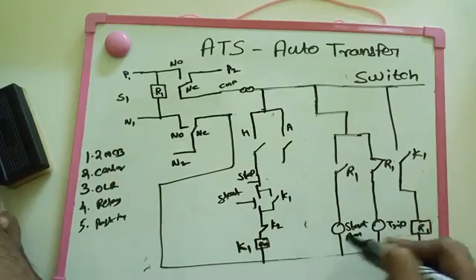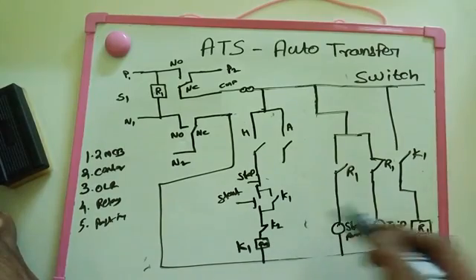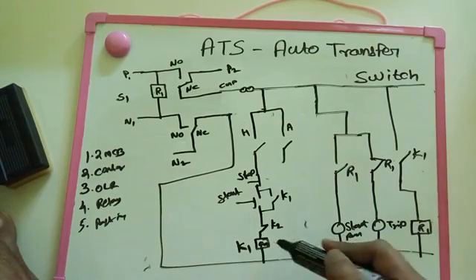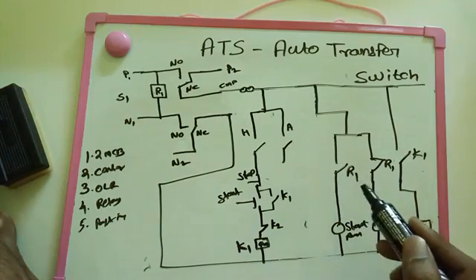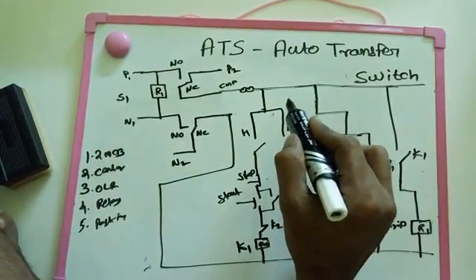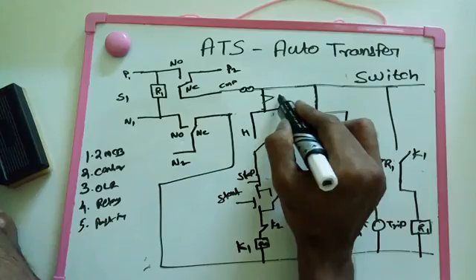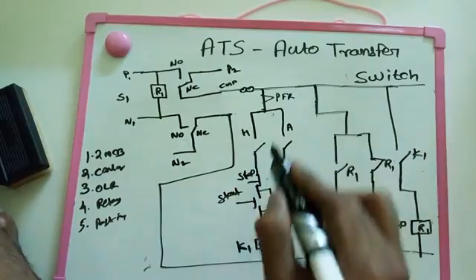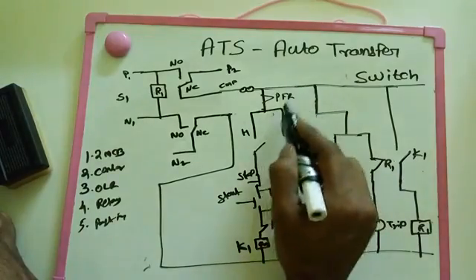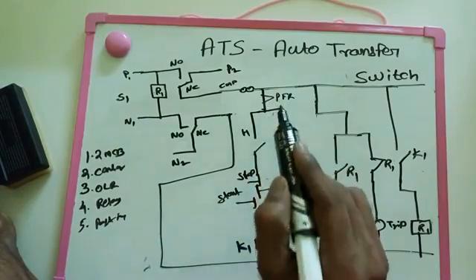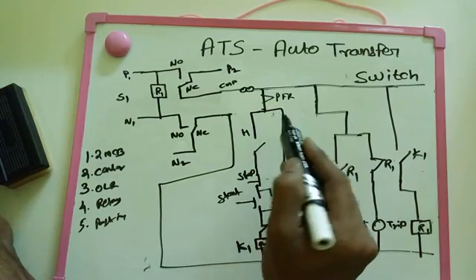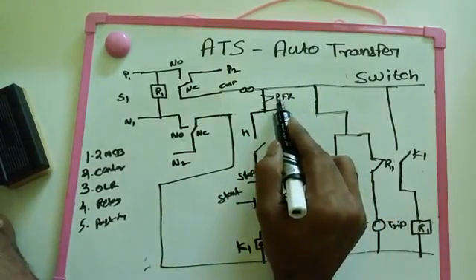If you start the main supply, the run signal will be showing on the outside indication lamp. When R1 is tripping - that means trip or stop - that one is showing. The ATS is a very big thing, so that's why it takes some time. The ATS panel needs a phase failure relay, because if a phase is lost - meaning only two phases are available out of three phases - this should not operate. So we need to put a phase failure relay which searches that all three phases are available. If three phases are not available, it will not switch on that supply.